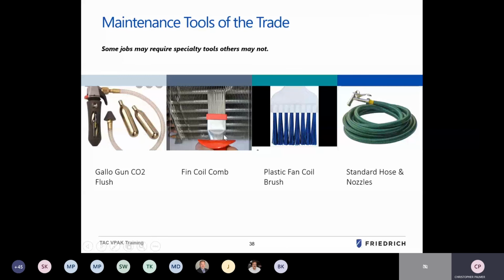Fin coil comb for straightening damaged coils or getting in between to try to straighten those coils. Keeping the coils nice and clean, keeping the airflow moving through, keeps the efficiency of the equipment up and benefits the overall operation of the equipment.